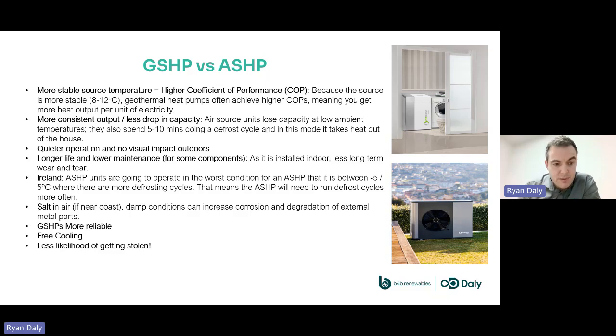The free cooling is a major plus with the ground source. You can do cooling with your air source, but it's active cooling, it has to run the compressor, and there's a cost to doing that. And then less likelihood of getting stolen. We've heard of a case recently in London where 27 air source heat pumps were stolen from a site on a Saturday, because these things are expensive and people are starting to get an awareness of what they do and how valuable they are.